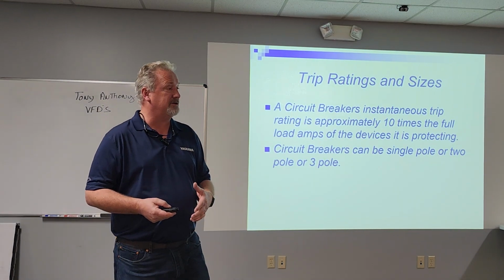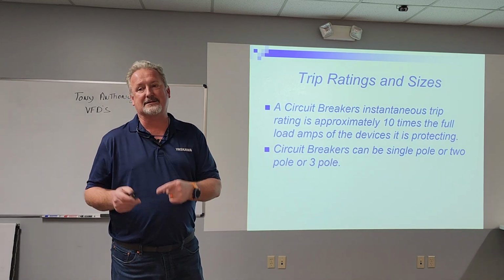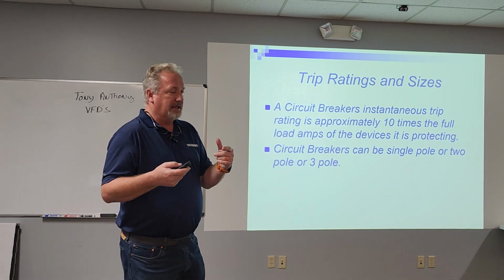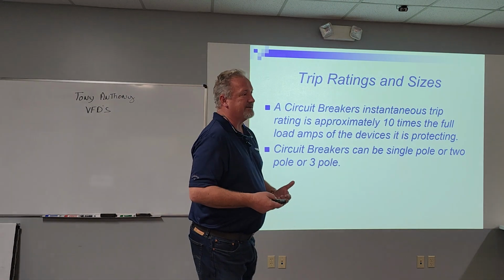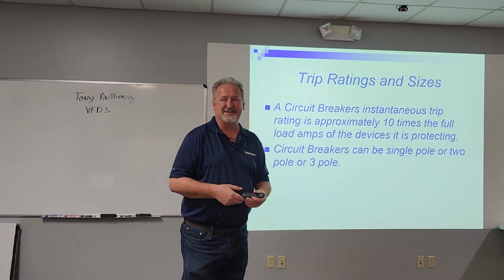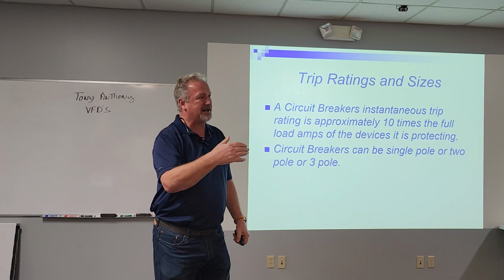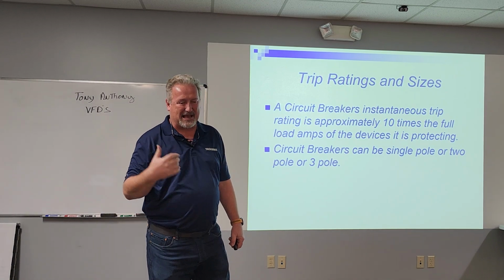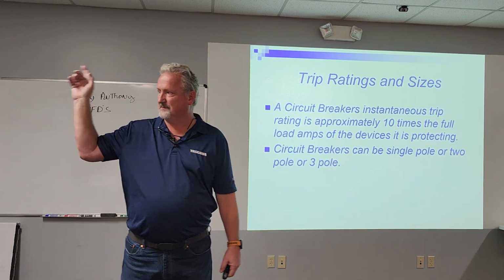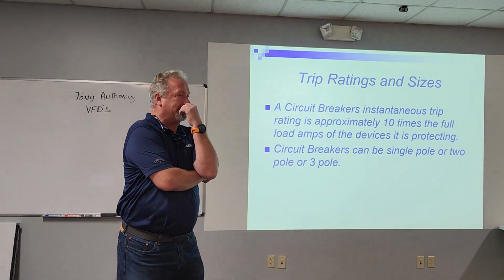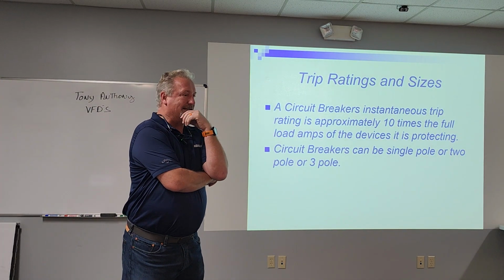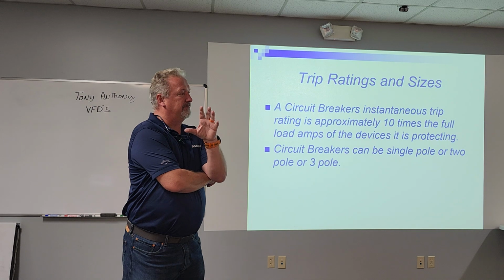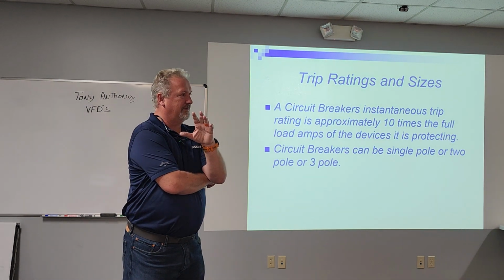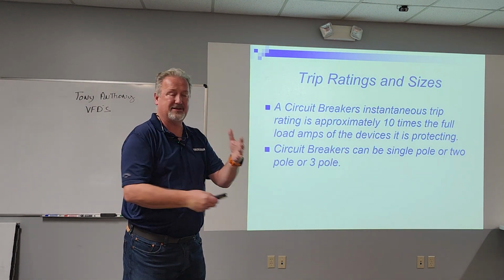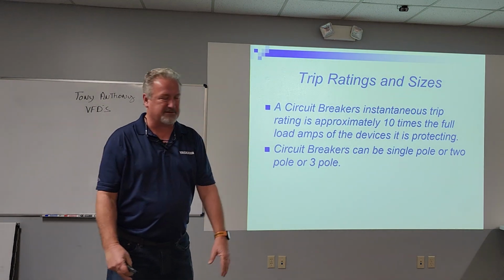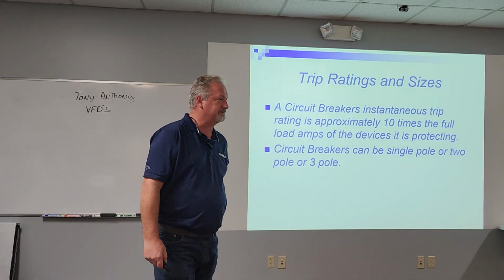Another thing about breakers, though: make sure you have the right style breaker. Some older style breakers don't trip fast enough for sensitive electronic equipment. So you can have a problem if you've got an old style breaker and you get a short circuit. This happened in a school district down around Akron. You get a call, we go in and look. They had mounted drives in a boiler room. They had mounted what we call type 1 drives, which are just finger safe, so there's no protection from water, on the wall right beside the boiler.